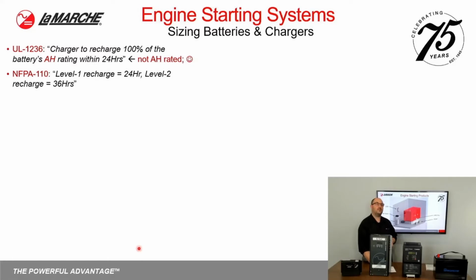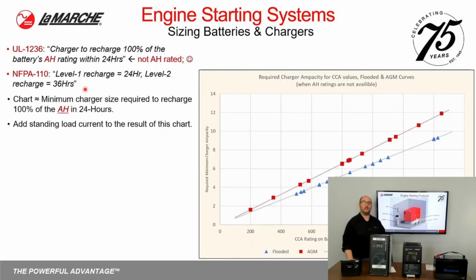So now that we've sized the battery, how do we work on the charger? UL 1236, here's a snippet, I just love this one. Within UL, they want you to be able to recharge the battery to 100% of the battery's amp hour rating within 24 hours. But the problem is, the batteries in this market segment are not rated in amp hours. You gotta follow the standards anyways. NFPA 110 says something kind of similar: for level 1, they want 100% returned in 24 hours. Or if it's a level 2 application, you can use a smaller charger that would return it in 36 hours. Although NFPA 110 doesn't specify amp hours, they imply that they want 100% restored.